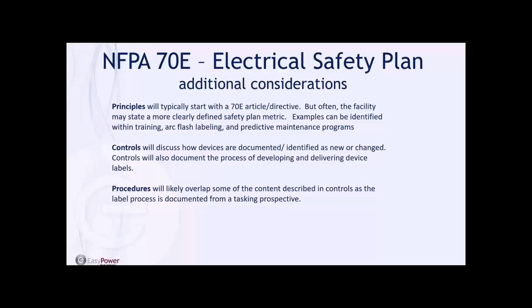The change out of equipment like transformers, for example: more efficient transformers have lower impedance values, and ultimately a change in a transformer should revisit the engineering calculations, because incident energy likely can be very different with a major change of impedance value. So those are examples of how a facility would go beyond the basic definition of 70E and define a facility principle, or how they're going to react to something.